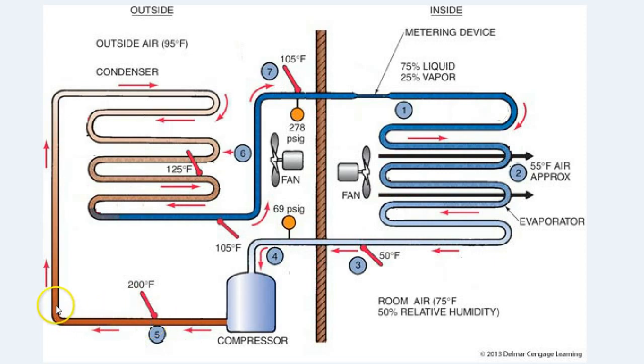At the beginning point of the condensing coil, we are de-superheating this vapor. It's going to drop the temperature from 200 degrees Fahrenheit. This is our sensible heat, so you'll be able to measure it. If you put a thermometer at this point, it might be 150. Then we hit a certain point here, and we're going to be at 125.